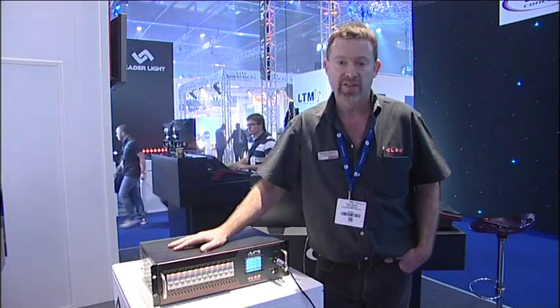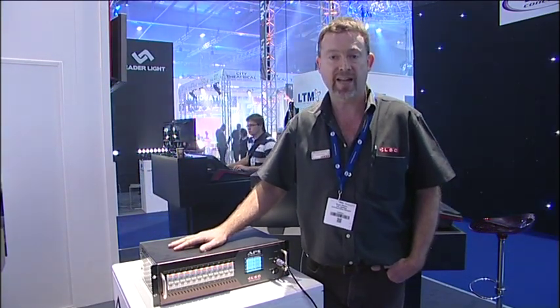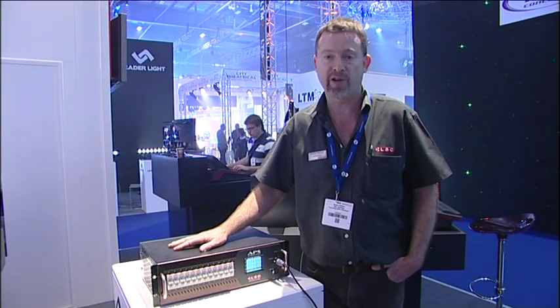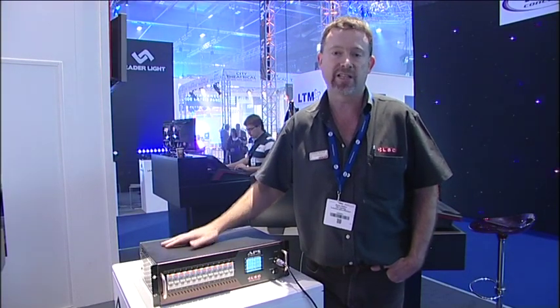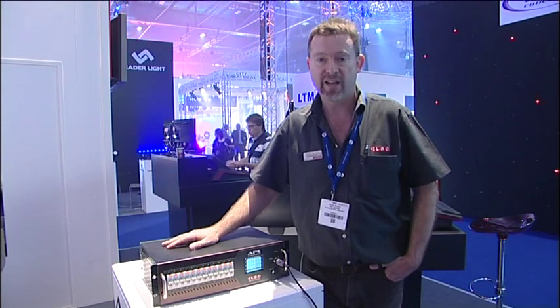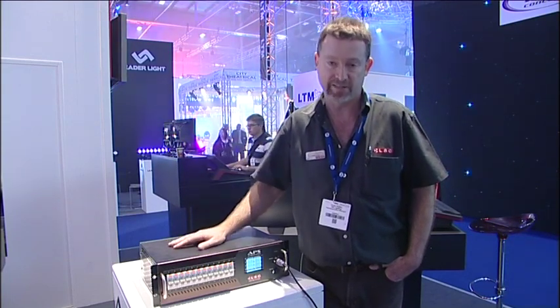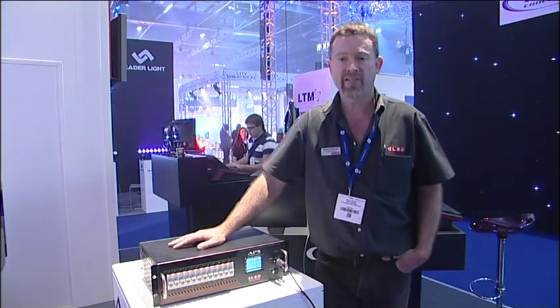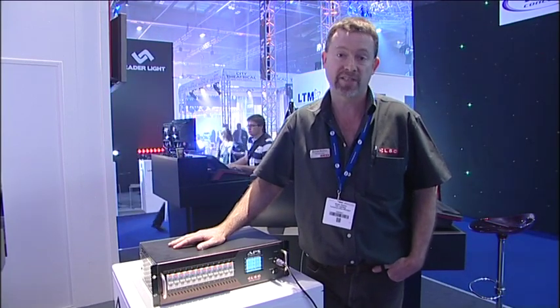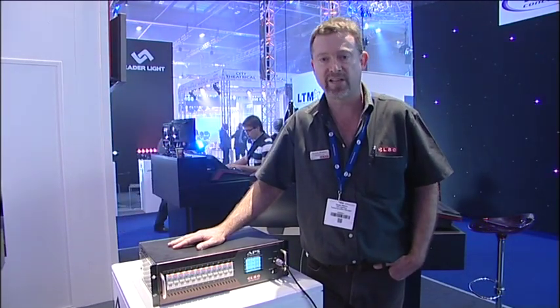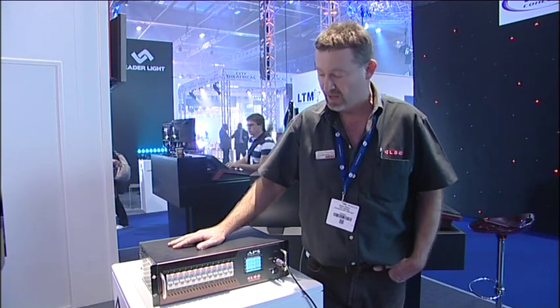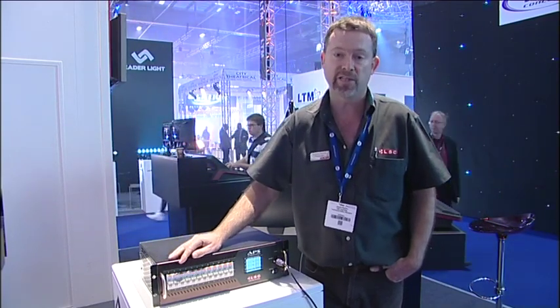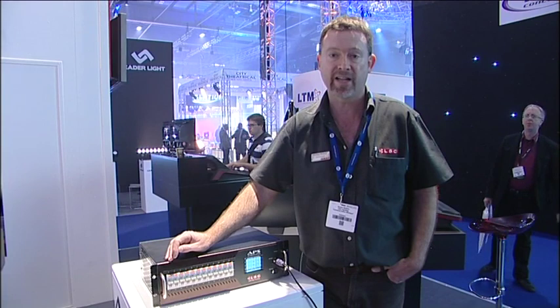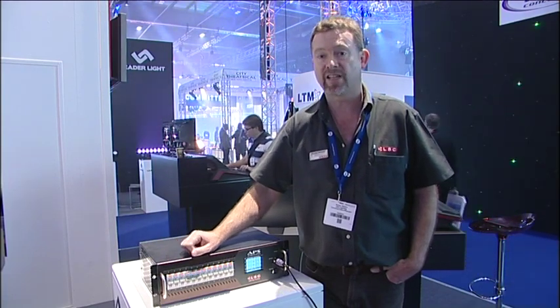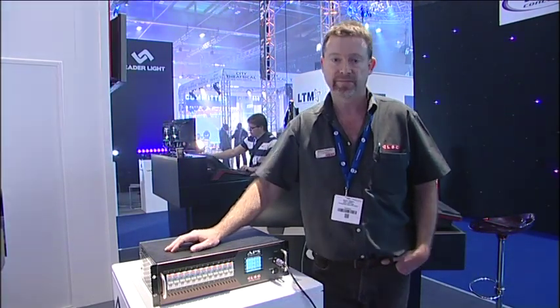of the show. The APS functionality includes the ability to set a maximum and minimum voltage and frequency for any phase to allow the system to automatically shut off the outputs in case the limits are exceeded. To meet current and future occupational health and safety requirements, as well as increasingly stringent electrical regulations, each and every output of the APS is protected by an individual 30 milliamp RCD and a neutral disconnect thermal magnetic circuit breaker.